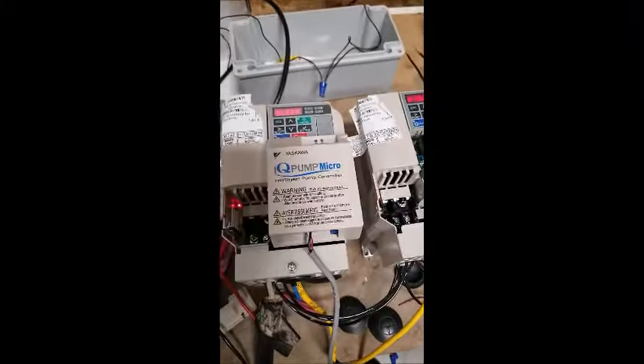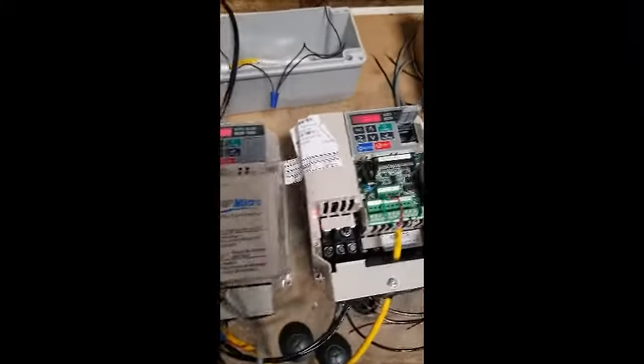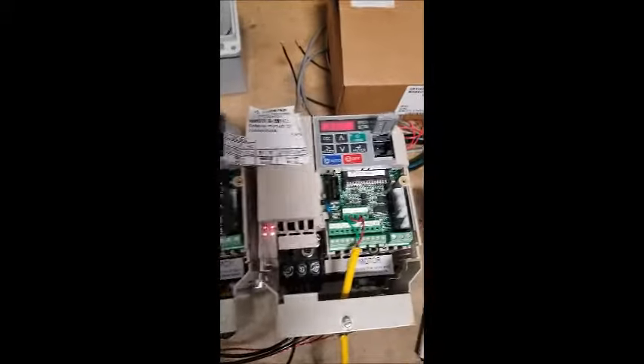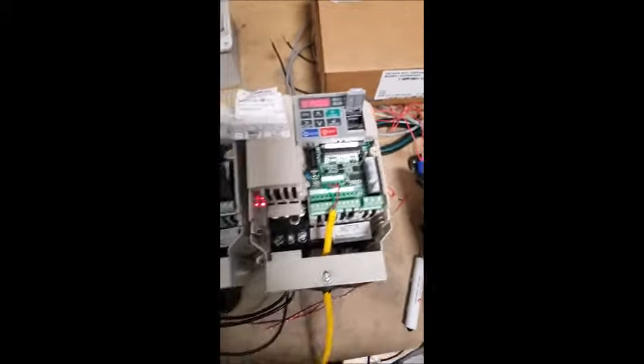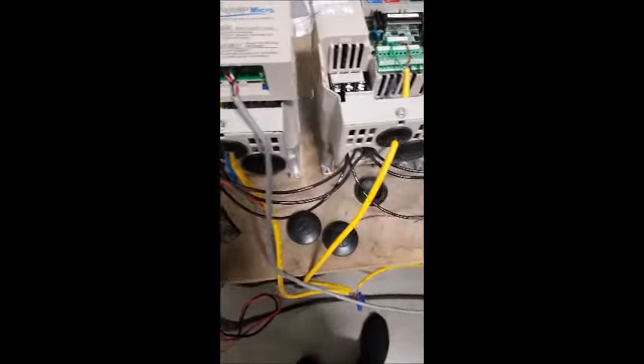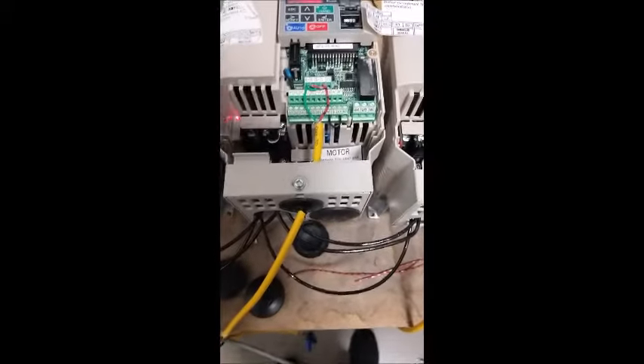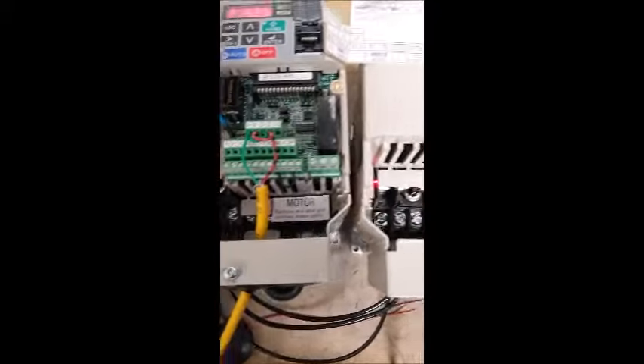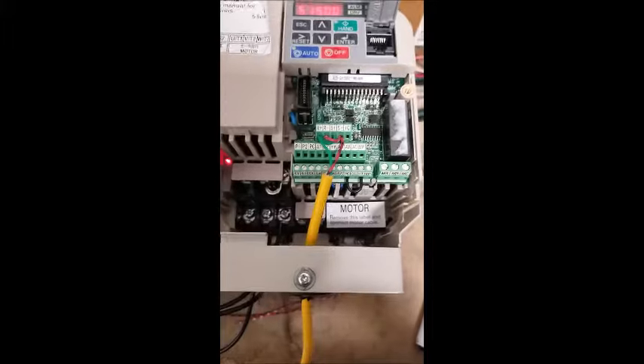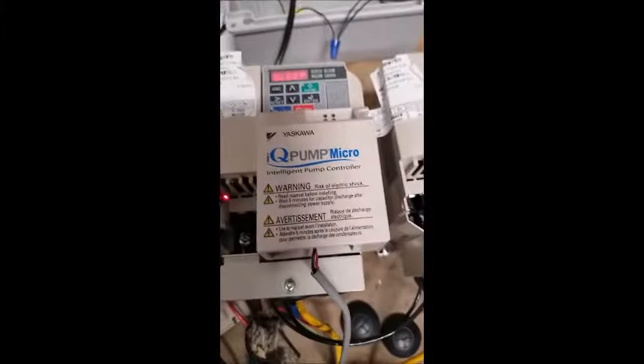Hi everyone, Kyle at Power and Control here, looking at 3 of the IQ Pump micro drives on my bench. I've set this up with communication wires between each drive into the RS-485 Modbus communication terminals so that we can stage these drives to work together.